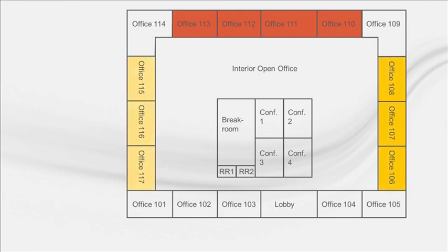Coupling offices 106, 107, and 108 on the east side with offices 115, 116, and 117 on the west side would probably make a poor choice due to the daily changes in load as the sun rises and sets, and the inability of the heat pump VRF unit to simultaneously heat and cool. However, a heat recovery VRF system can heat and cool zones simultaneously, and it can use the recovered heat from one zone in cooling to heat another zone.